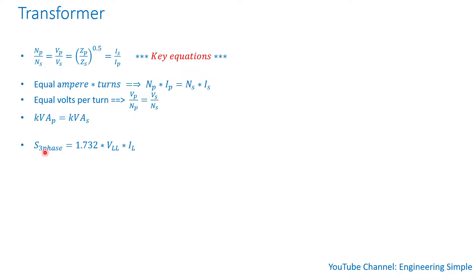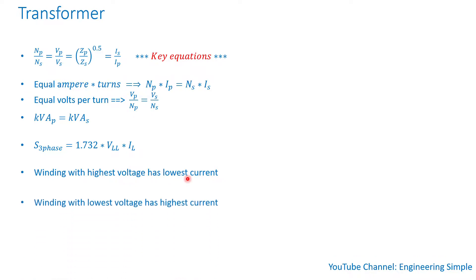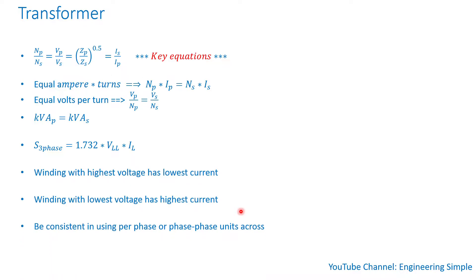Three-phase apparent power is equal to √3 times the line-to-line voltage times the line current — that's how you calculate three-phase apparent power. The winding with the highest voltage has the lowest current, and the winding with the lowest voltage has the highest current. When dealing with transformers, you want to be consistent in using either per-phase or phase-to-phase units.